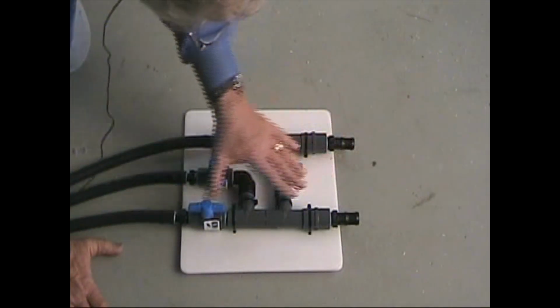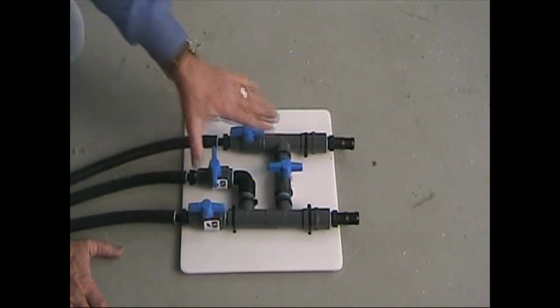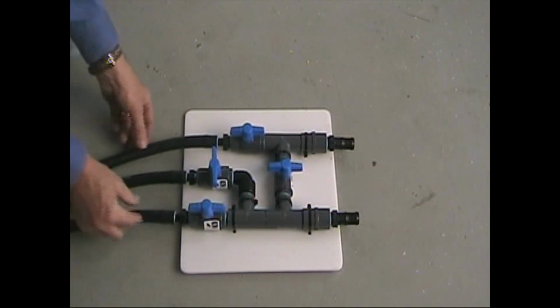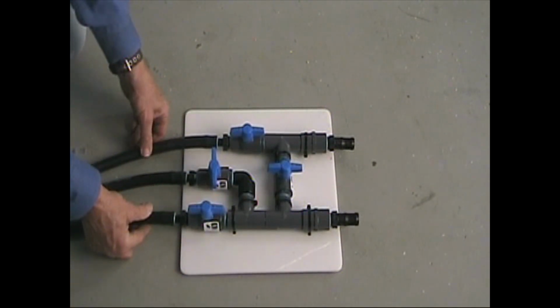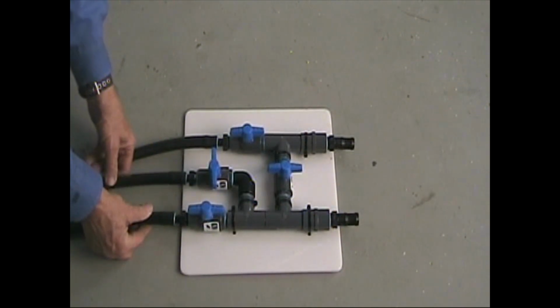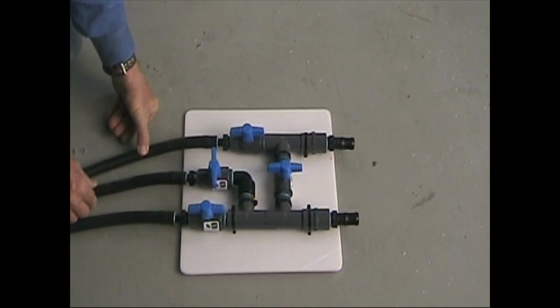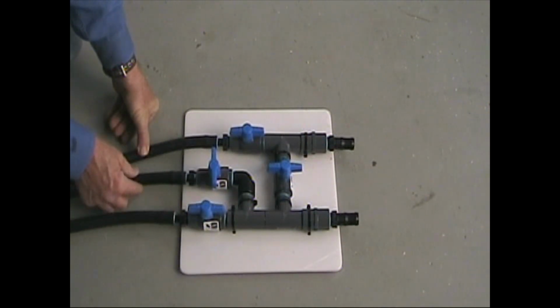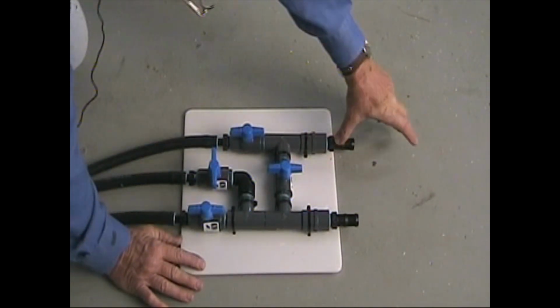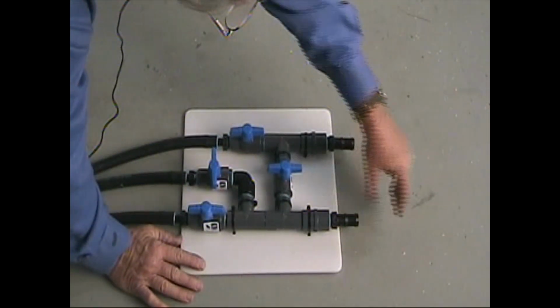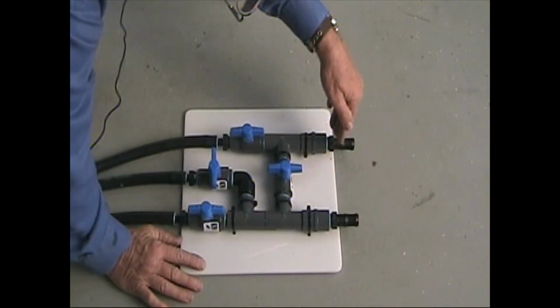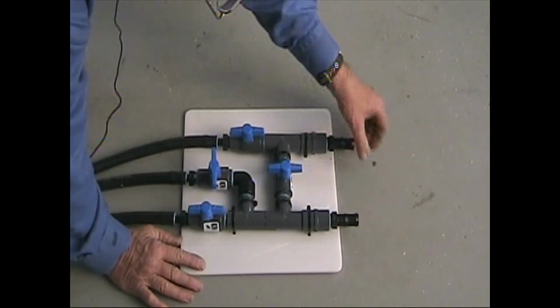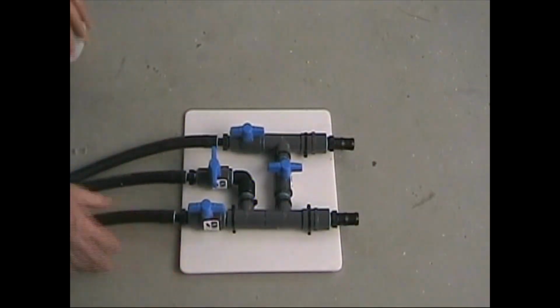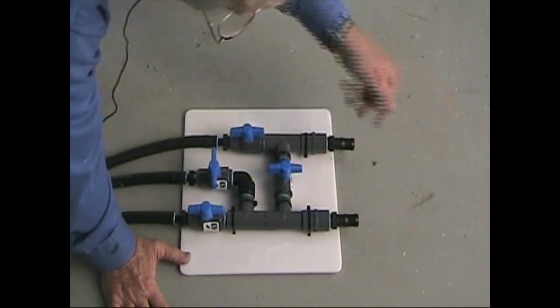Last thing you're going to do is connect your suction lines to the tanks. This is a suction manifold, and these two lines here, this one and this one, go to each of the pump heads. This third line is a line that you can use to flush out the pump head or use to inject a third product, a wetting agent or something from a drum. Then your two main lines go here, and they'll have Y strainers in them between this and the tank. You use hose clamps on these hoses, the red hoses. These don't use the hose clamps because they're push lock, but the red hose needs the clamps, which we supply.